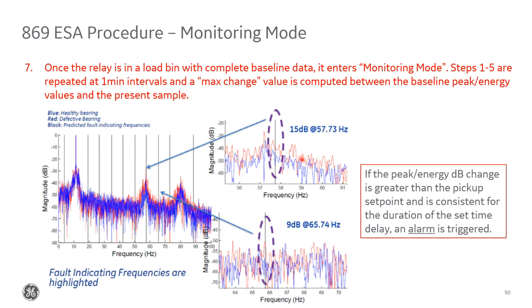For the identified fault frequencies, we look at what the difference between these two values is. And if this difference exceeds the pickup set point we entered, and this difference is present for the duration of the time delay that we set, then an alarm is triggered on the relay that gives the user an indication that something is wrong and the motor should be looked at. And that's basically all there is to the ESA feature procedural wise.